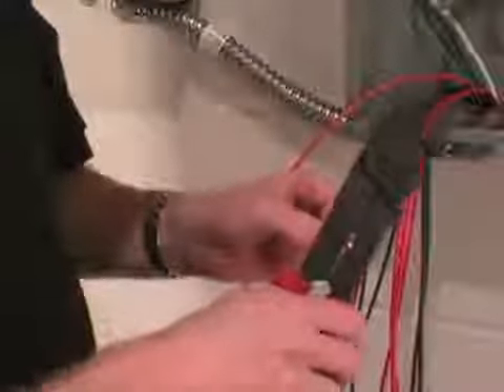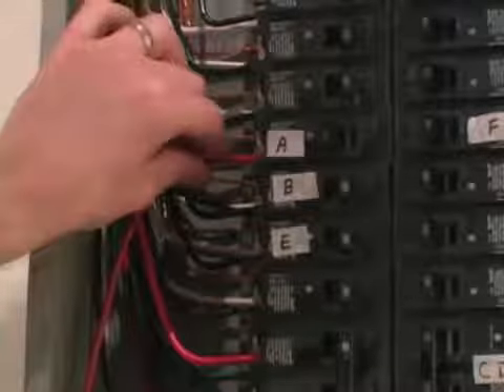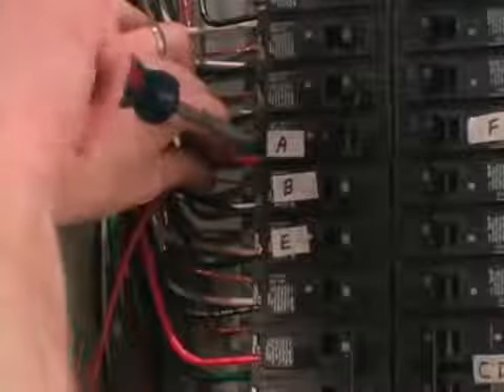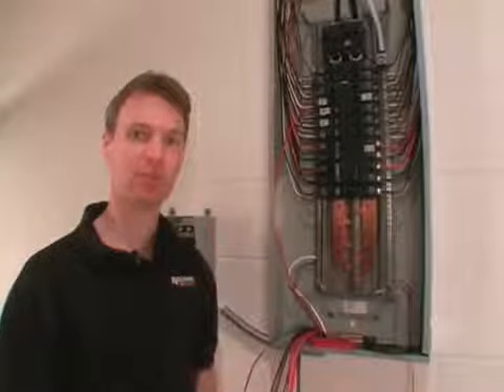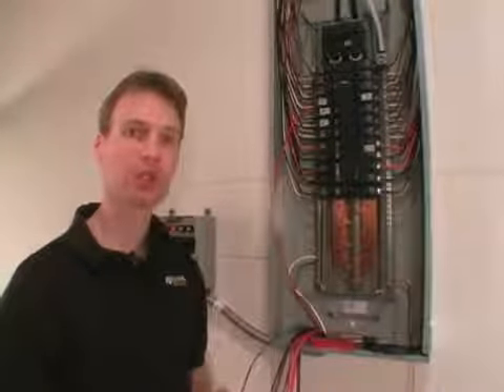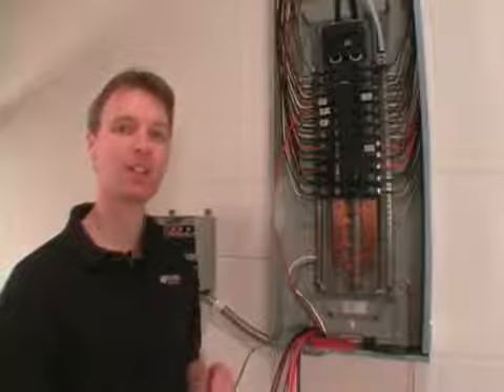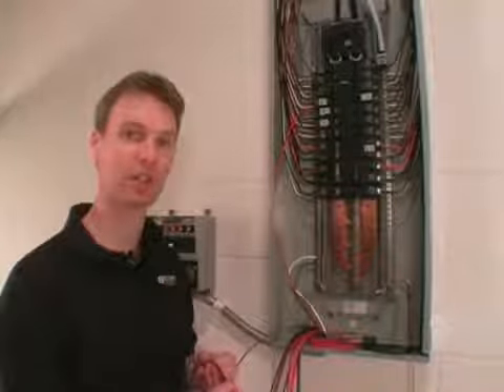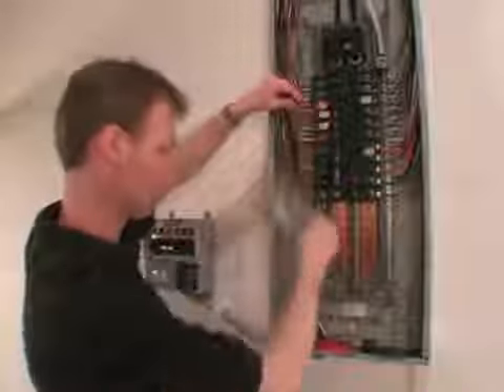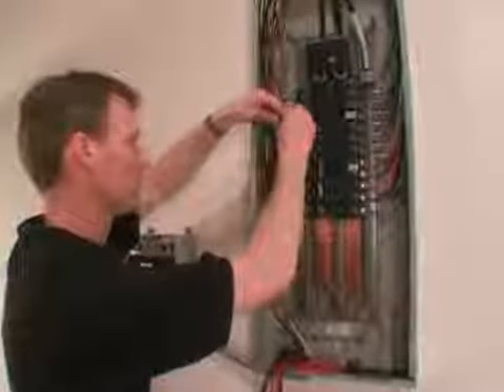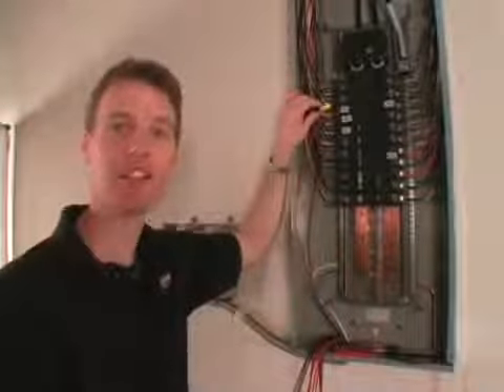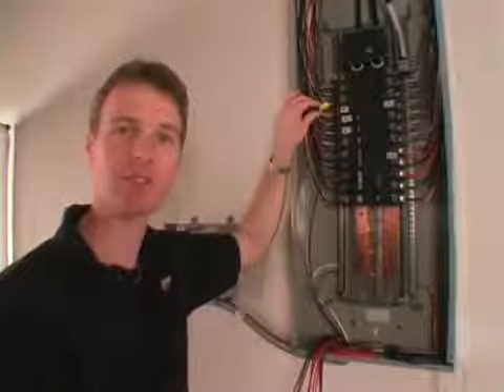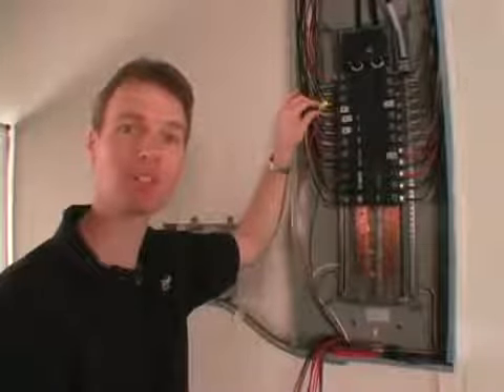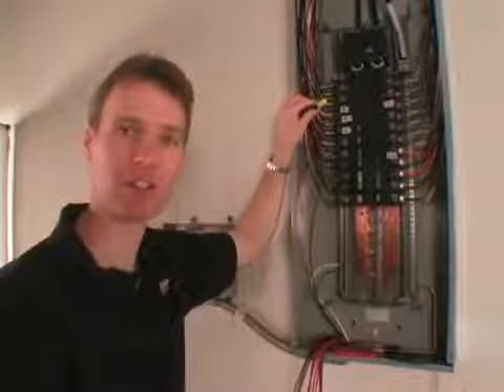Strip that wire about 3/8 of an inch and connect it to the furnace breaker. Finally, we'll take the black wire labeled A from the transfer switch, cut it to an appropriate length, strip it, and use a wire nut to tie it to the wire that we removed from the furnace circuit breaker. The A circuit is now wired to the furnace through our transfer switch. We can now repeat this procedure for the other 120 volt circuits.